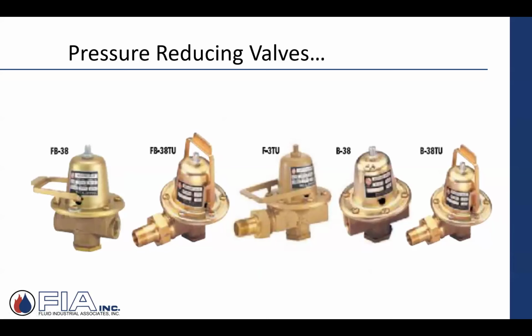Next device that we want to talk about is a PRV, a pressure reducing valve. A fill valve is another term you'll hear out in the industry, but basically their job is to take city water, city pressure, and knock it down, reduce it to what the particular system it's being attached to needs to fill that system. It's a hydronic system. We need to have water everywhere. And most importantly, all the way to the high point.